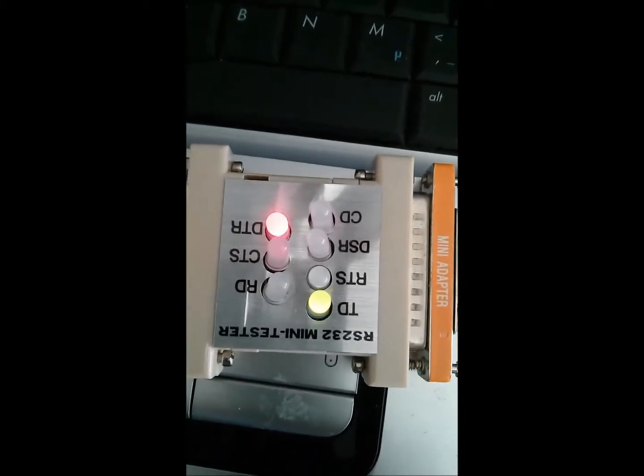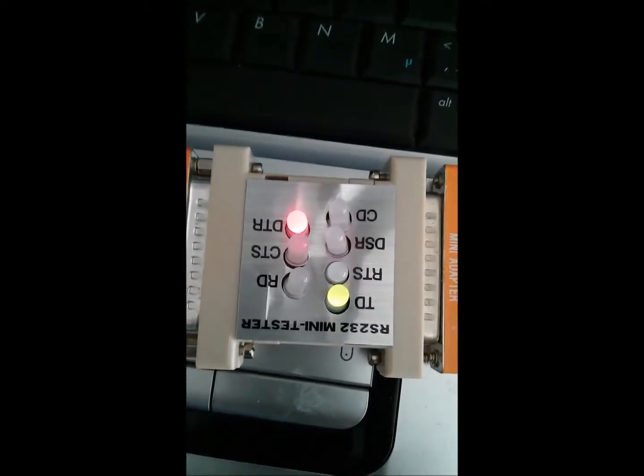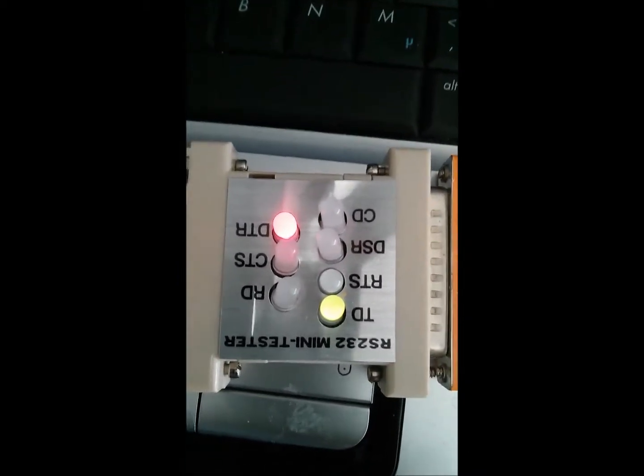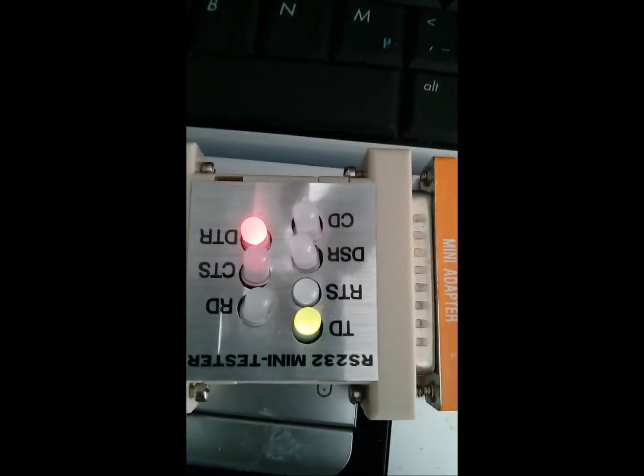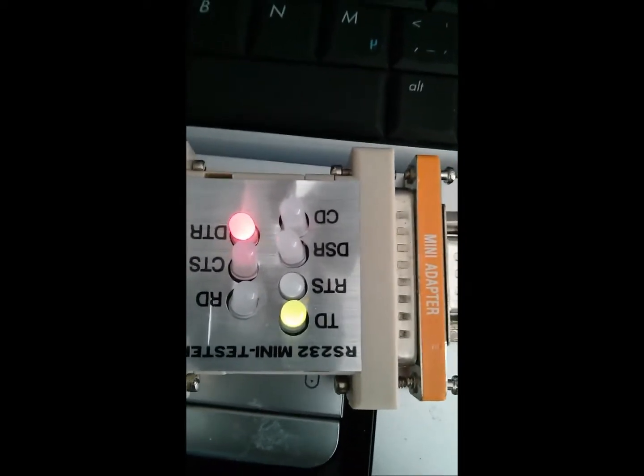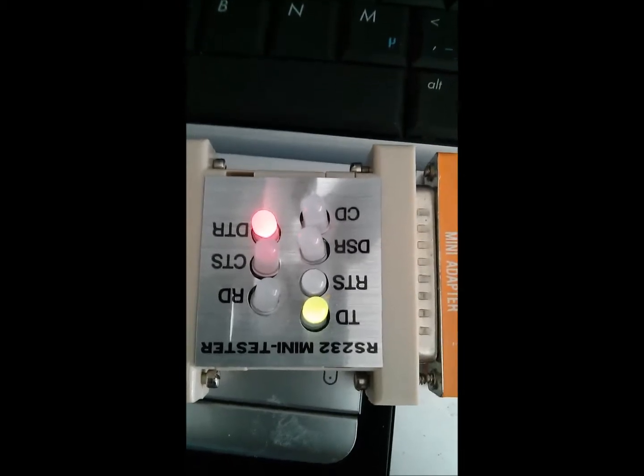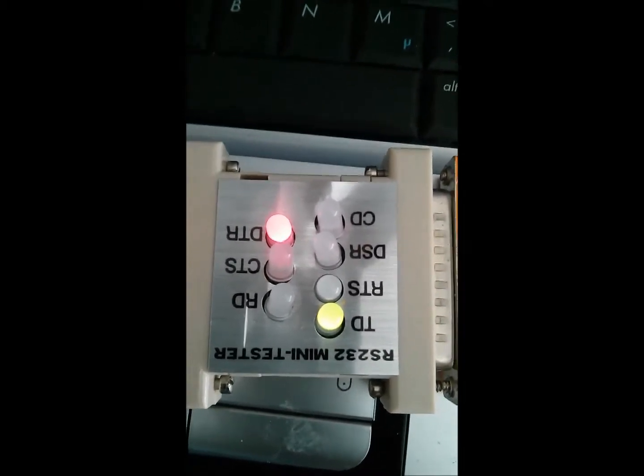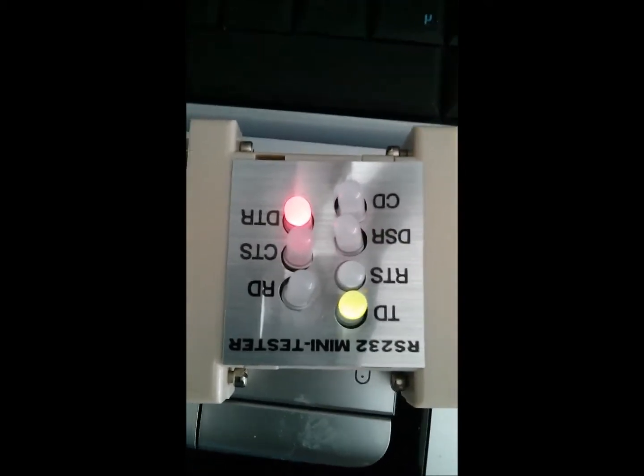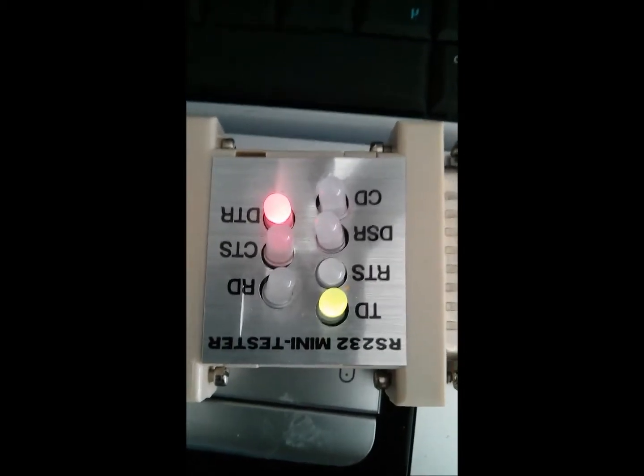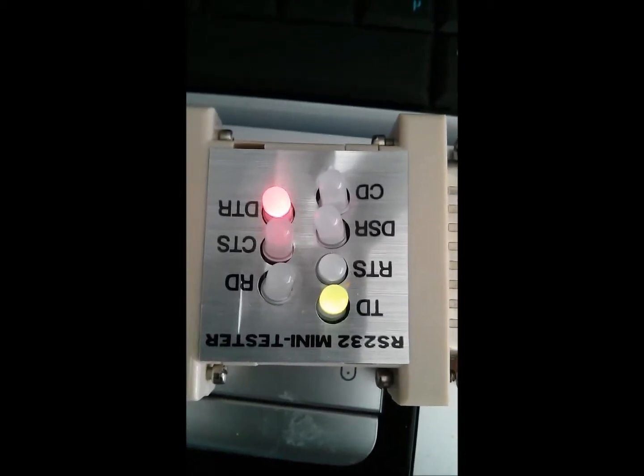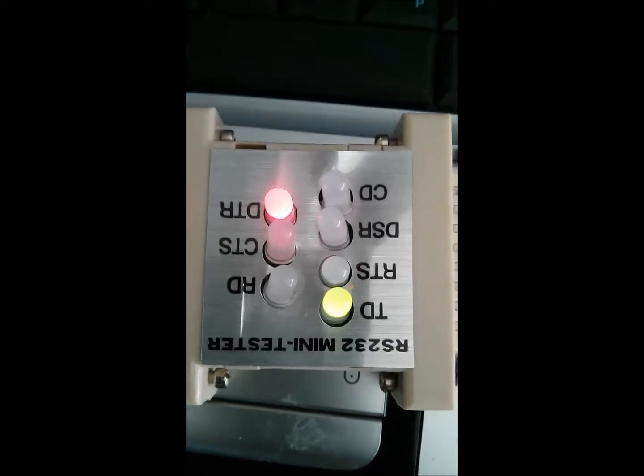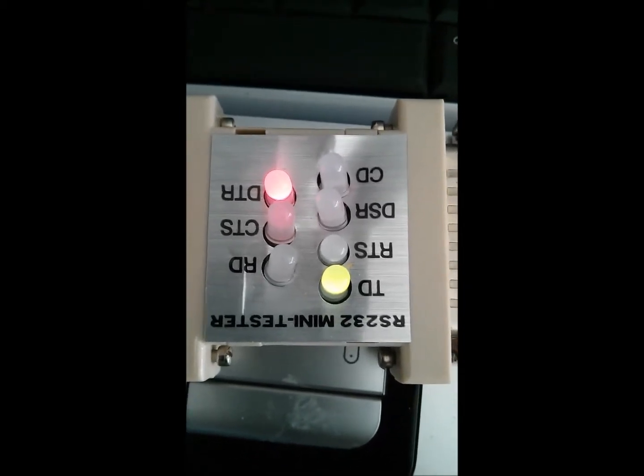That is the carriage return character, an attempt to synchronize the baud rates between the RLink and the FieldServer gateway. It does flicker once every second, and about every 30 seconds, when the gateway tries to re-establish connection with the RLink if it isn't connected, we should see the DTR light flick for a short period of time. Perhaps too short for us to actually see, so I'm going to show you on the scope.